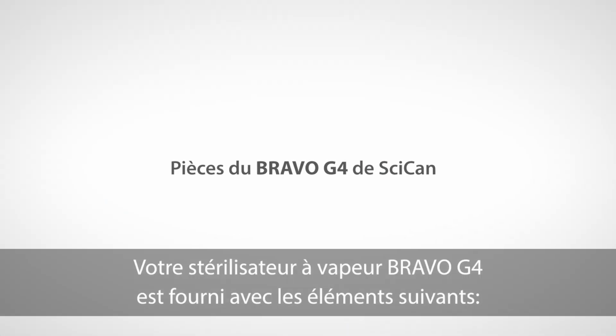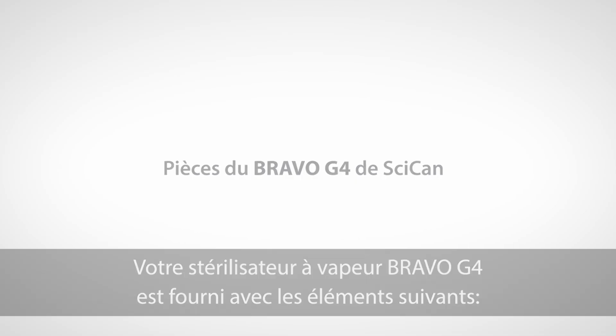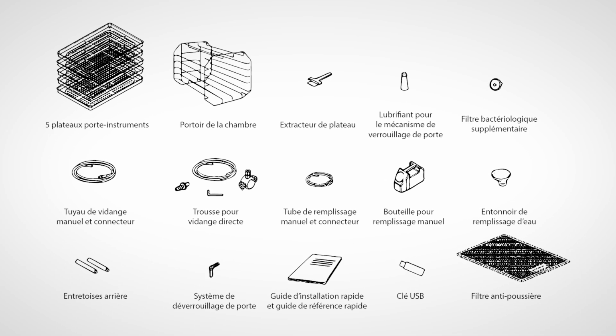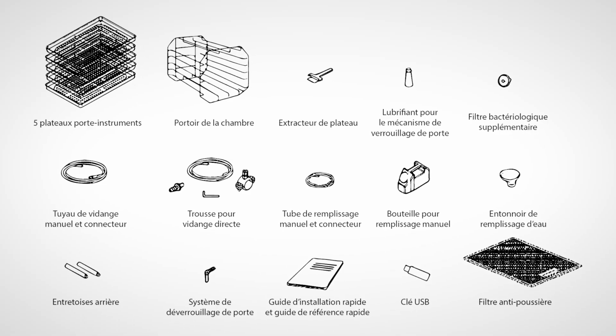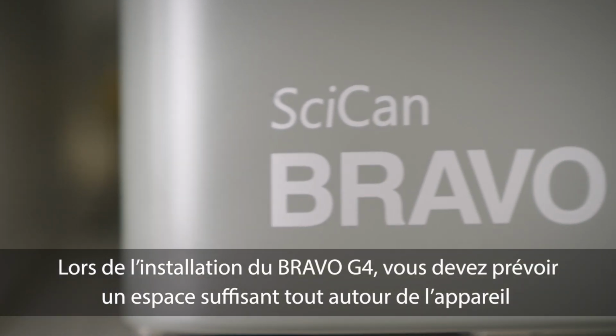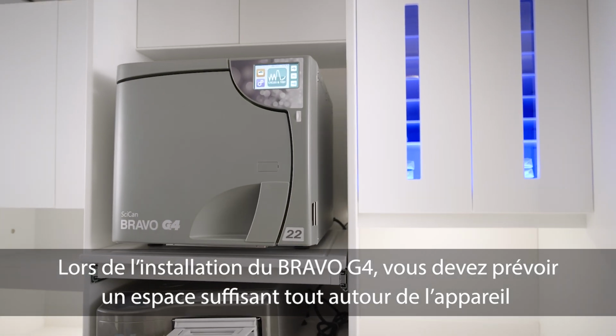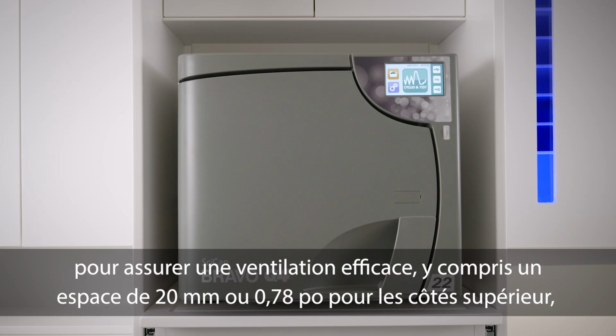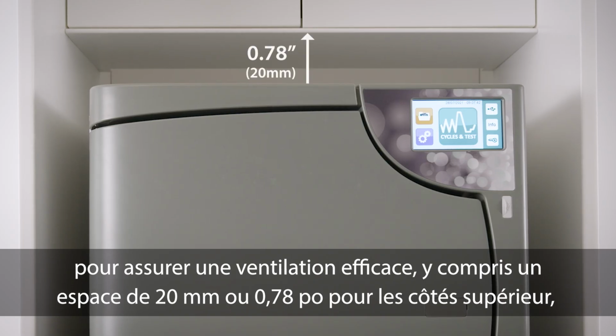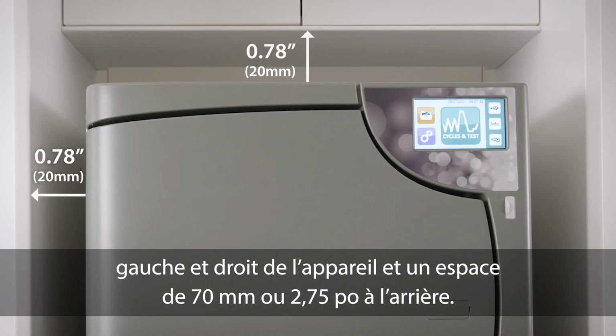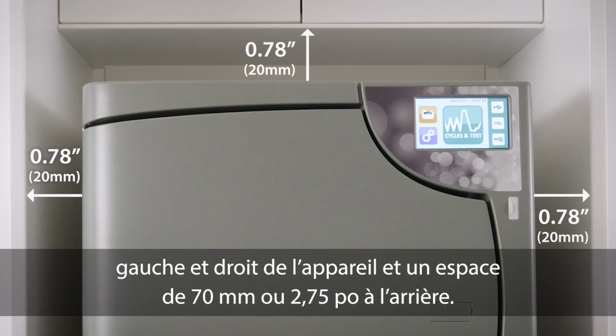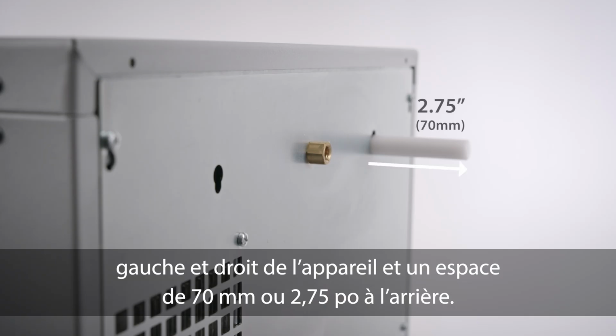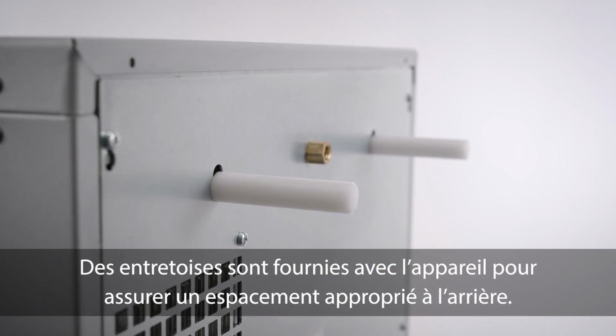Your Bravo G4 steam sterilizer comes with the following items: When installing the Bravo G4, ensure there is adequate space around the machine to provide effective ventilation, including 20 mm or 0.78 inches space for the top, left, and right sides of the machine, and 70 mm or 2.75 inches space at the back. Spacers are provided with the unit to ensure the proper spacing at the back.